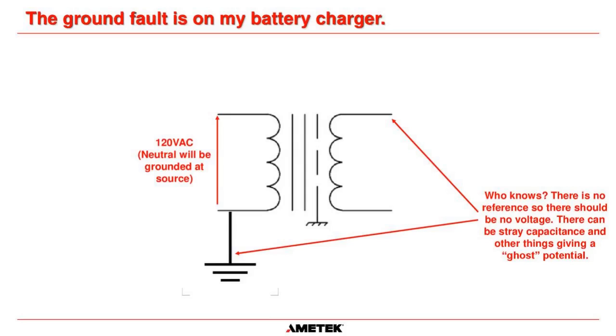Another question is, is the DC panel with chargers and batteries connected covered under a certain article of the NEC? For example, you mentioned an oil pump application may have no circuit protection between the panel and the battery. Is that allowed by the NEC? That's a very good question, John, and I would have to get back to you on that. I'm not an expert on the National Electric Code, because in many of the situations that we work in in the petrochemical industry, the NEC code doesn't quite apply to many of the industrial situations. Just local codes apply. So I can't answer that question, but I will ask engineering.